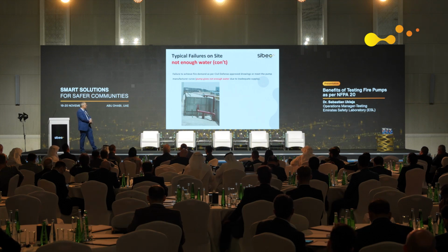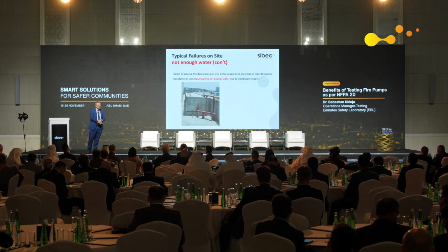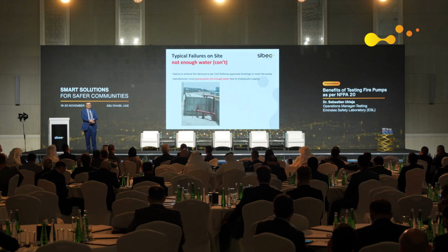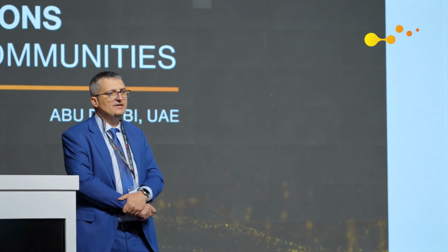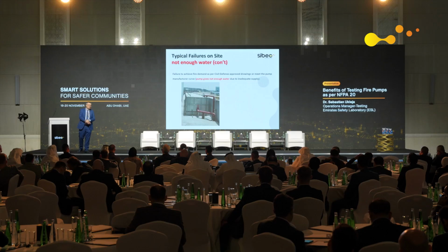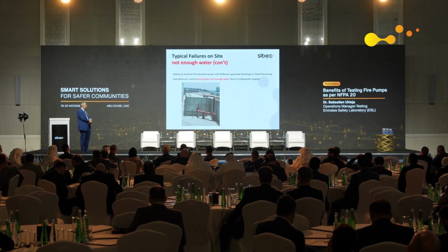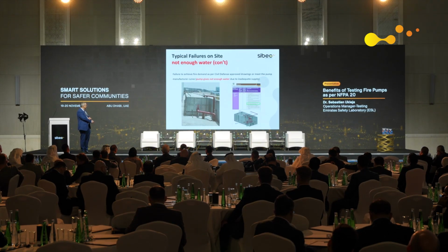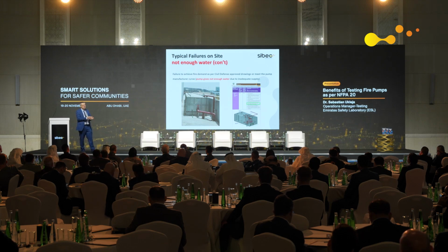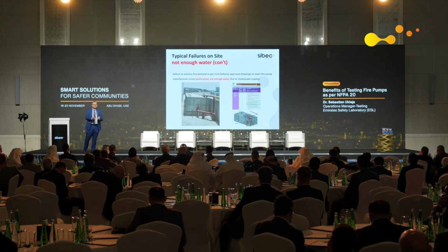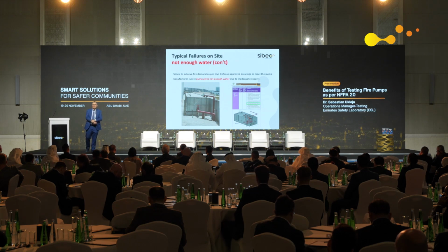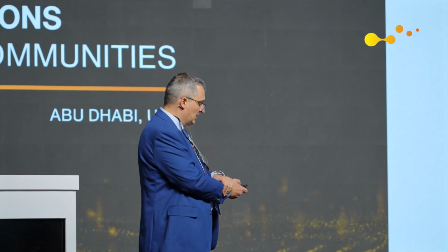Less sophisticated examples: the UAE code, and I guess not only here, requires that there should be two water pipes coming from the water tank to the common header and then the pumps. Sometimes, especially with a warehouse, we see only one pipe. Sorry, that's the laser. So it's only one pipe, which means pressure losses, friction, and that gives the situation that the pump is not getting enough water.